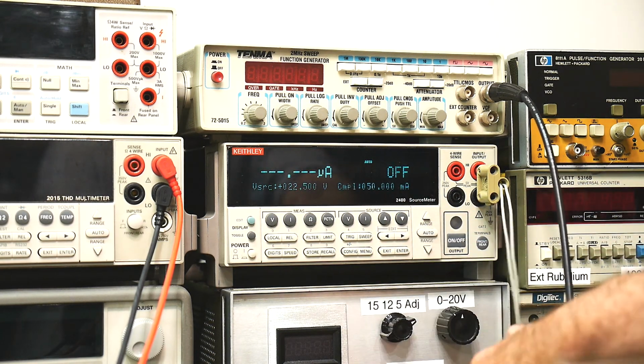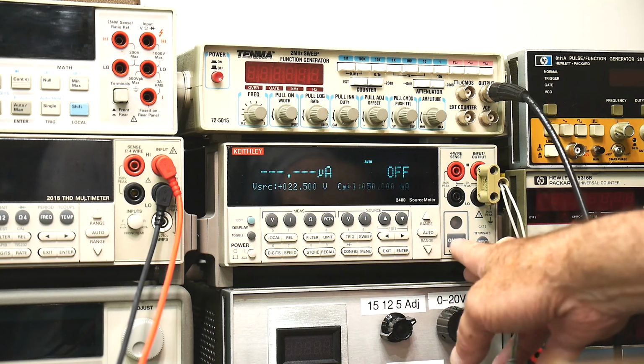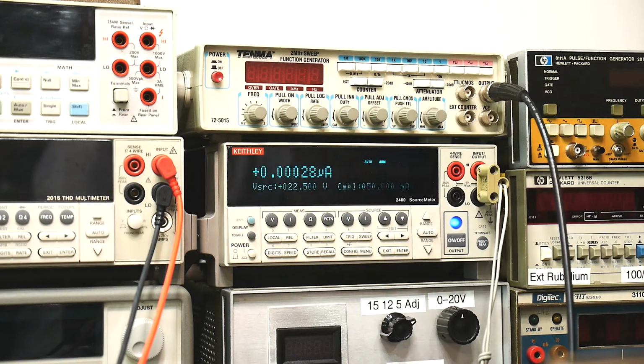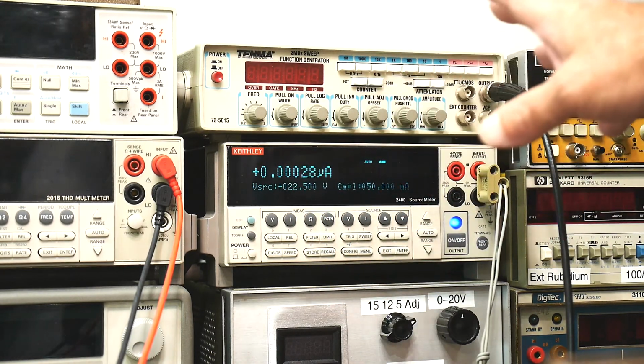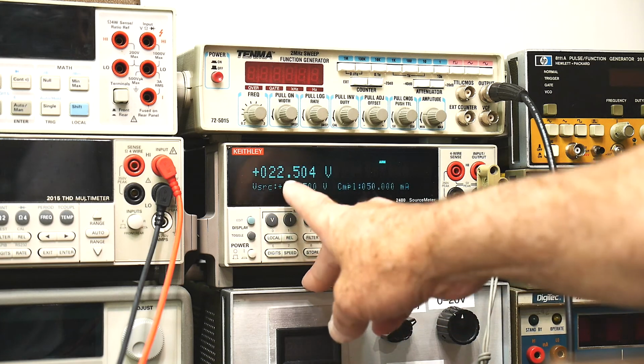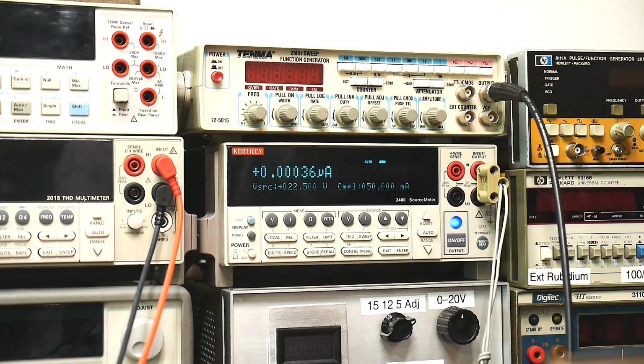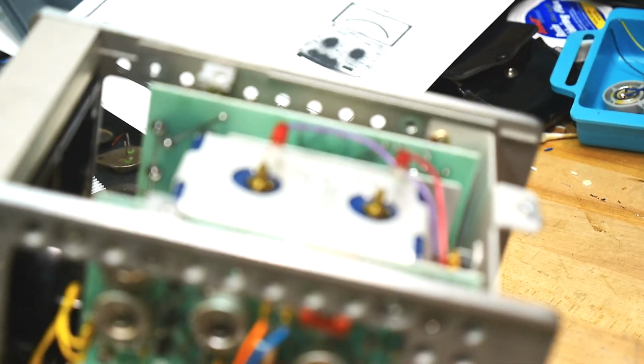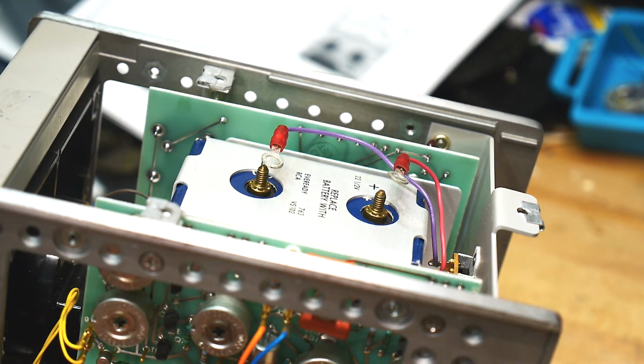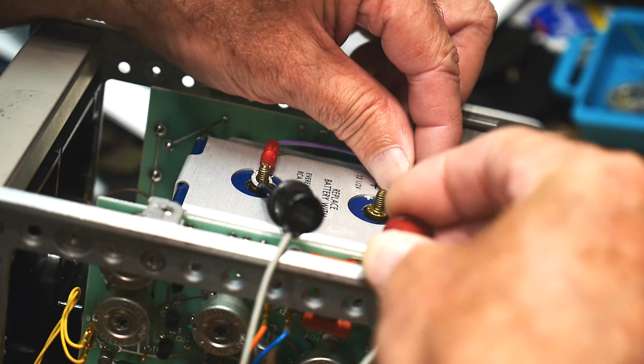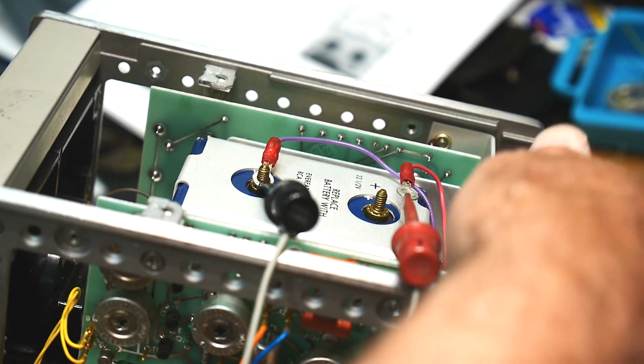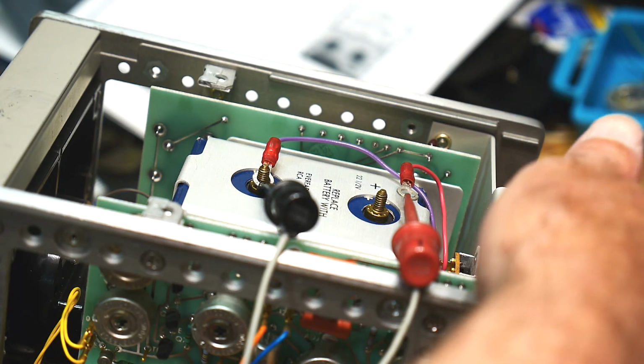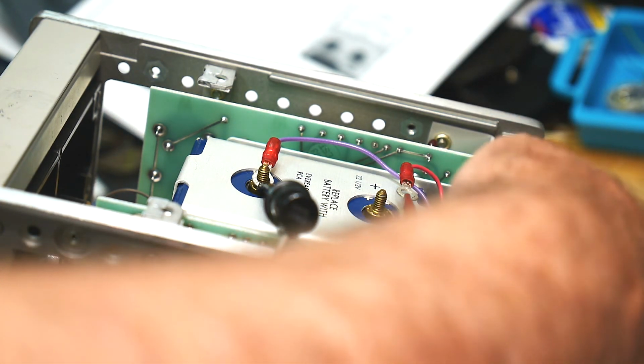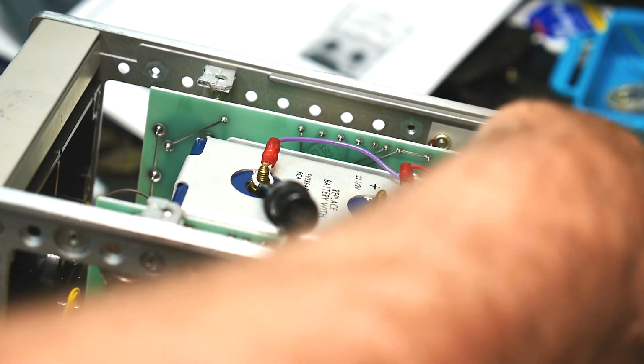If I hit this button, it turns it on. So let's go ahead and do that. No harm there. So we're measuring the current. We could measure the voltage by hitting this button, 22.5. Measure the current, it's nothing. So let's go ahead and hook up the minus lead and the plus lead, and we will turn the unit on. It's in battery mode now.